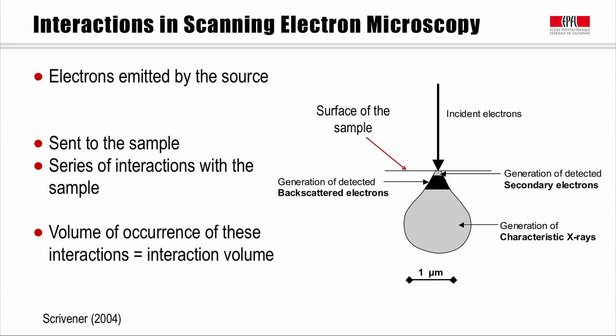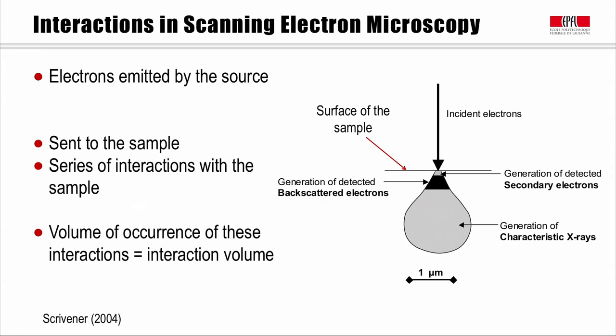In a scanning electron microscope, electrons are emitted from the electron source, they pass through a series of lenses which focus them, and then the electrons reach the surface of the sample. They undergo a series of elastic and inelastic collisions with the atoms of the sample. Different signals can be collected from these collisions. In a scanning electron microscope, the surface of the sample is analyzed point by point, and the final image is the assemblage of the information from all these points.